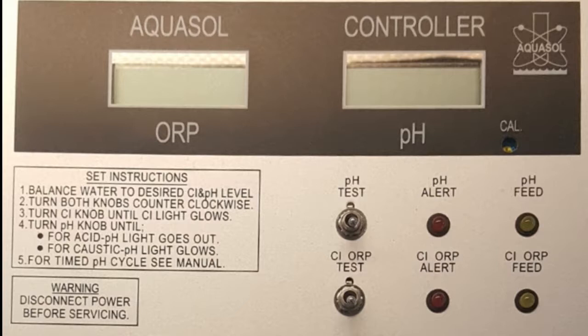Next, we have your pH alert LED. When this LED is lit, the controller is indicating that the signal coming from the pH electrode is out of range of the pH control knob. The pH alert overrides the pH feed system. At that point, the controller cannot make pH adjustments when the pH is in alert.